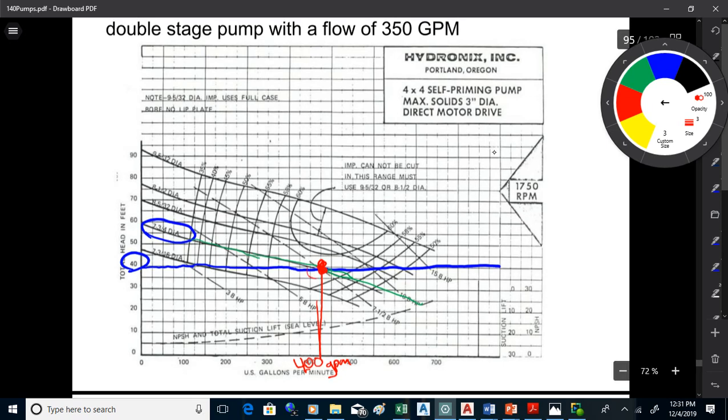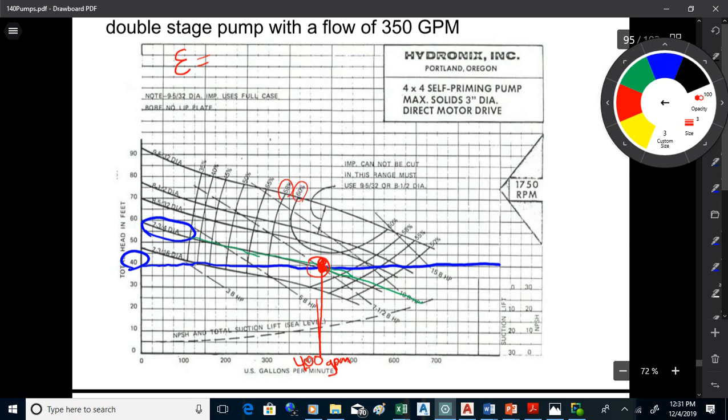Now, we're right about here. These efficiency lines are running through there and there. They're curves that kind of run through. Which efficiency lines are we between right now? 58 and 60. So efficiency is often shown with a backwards 3. That's a Greek letter epsilon. It means efficiency. 59%, near enough. Okay.